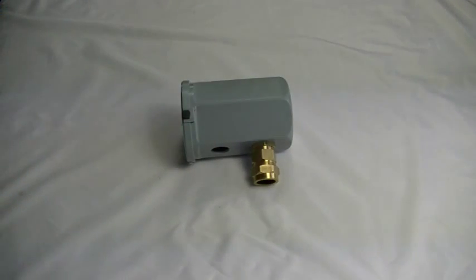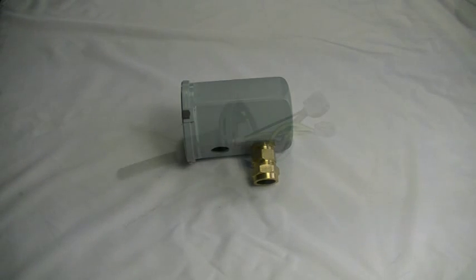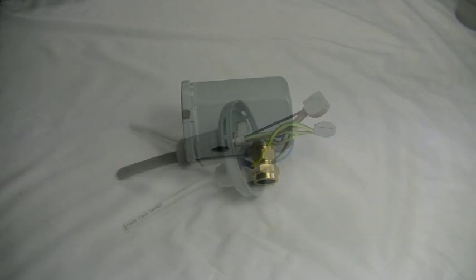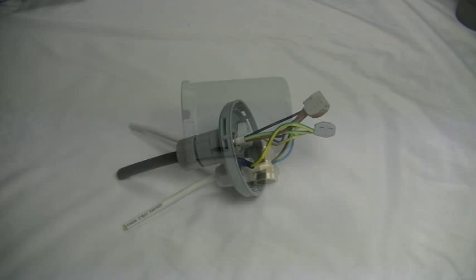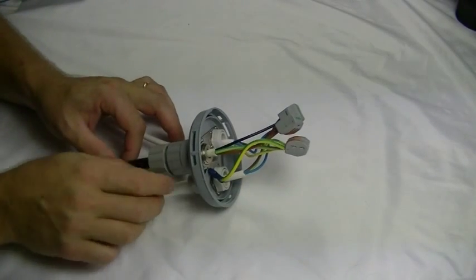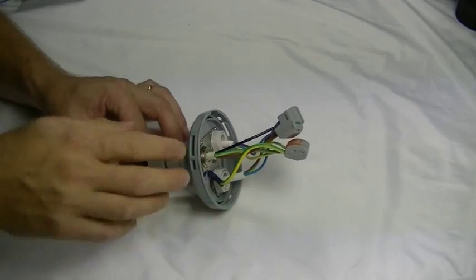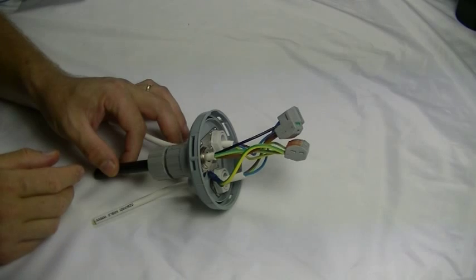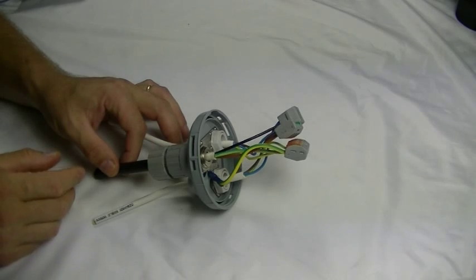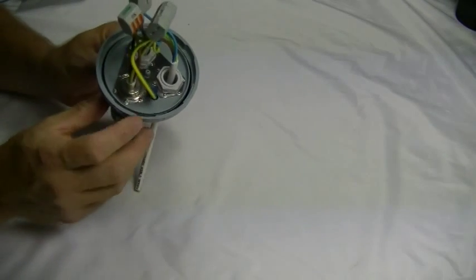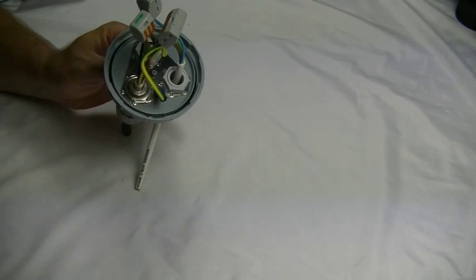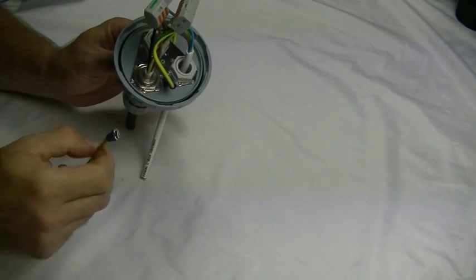Once the glands have been fitted, we're ready to install the cables. When fitting cables to the lid, the length of the core inside the capsule should be approximately 90mm. Note that the bonding plate can be connected using a standard crimp spade terminal.